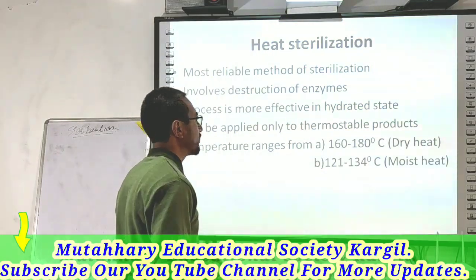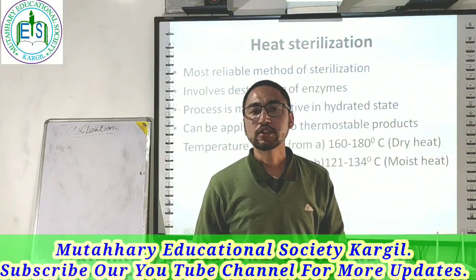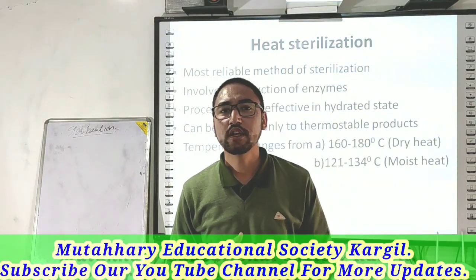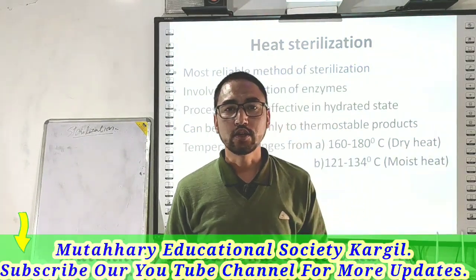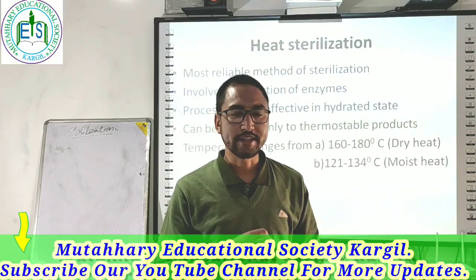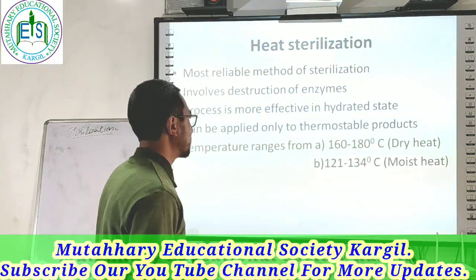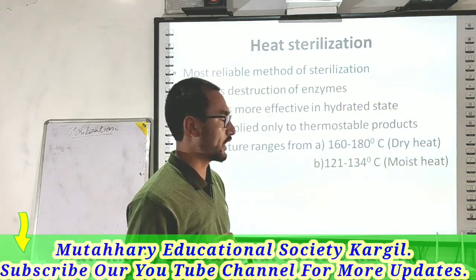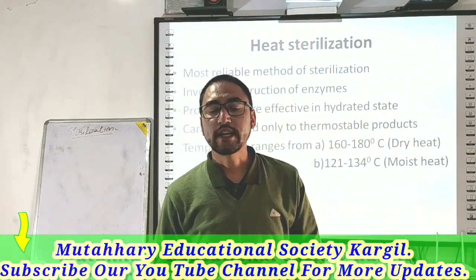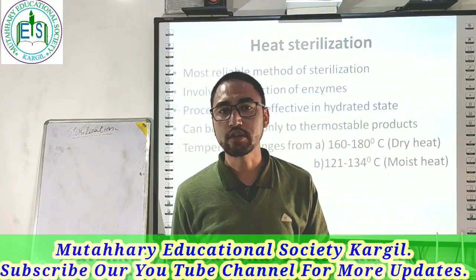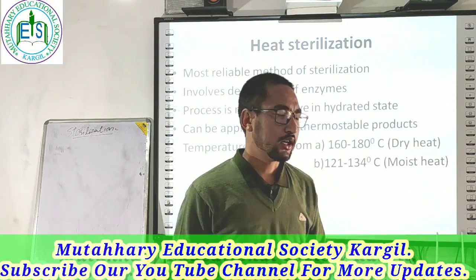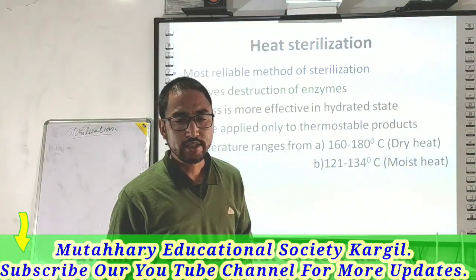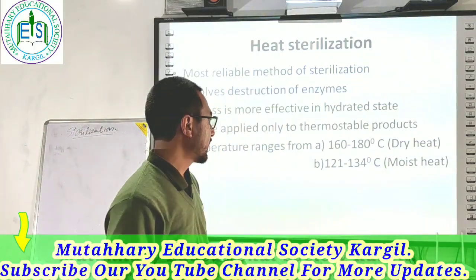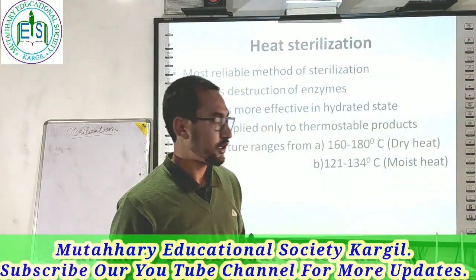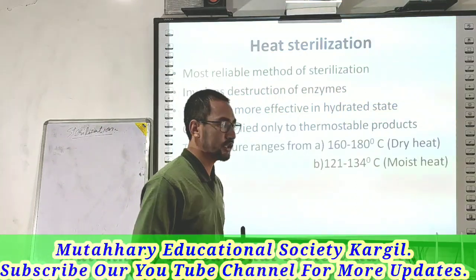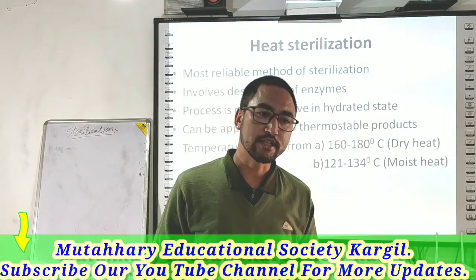So it can be applied only to thermostable products. That means those substances which can resist temperatures of around 100 degrees Celsius and above, only those substances can be sterilized by heat sterilization. The temperature ranges from 160 to 180 degrees Celsius for dry heat. That means you do not use any steam or moisture or water, there is only dry heat, meaning you are using some kind of oven. Moist heat is also there, where the temperature ranges from 121 to 134 degrees Celsius because of the excess pressure of the steam.